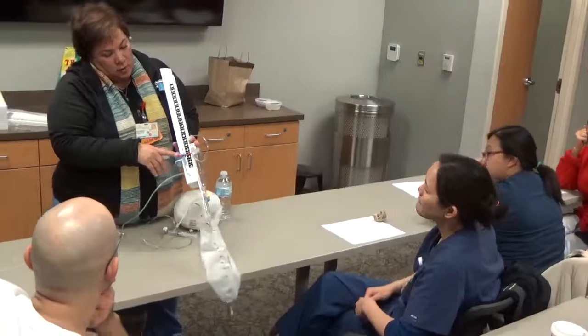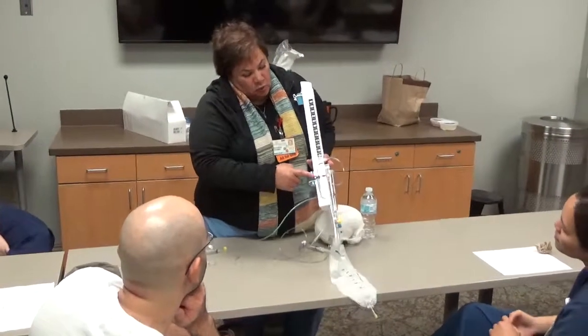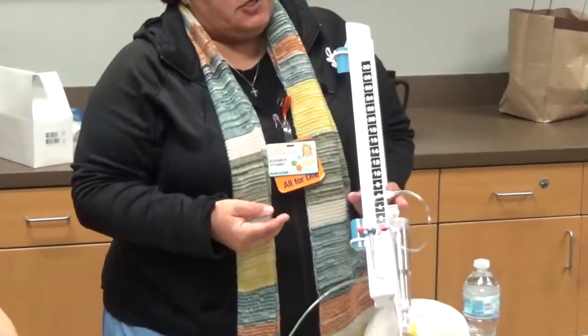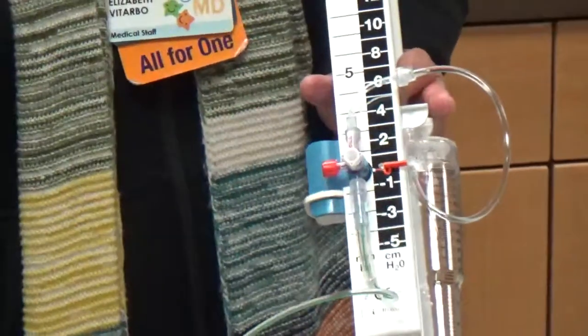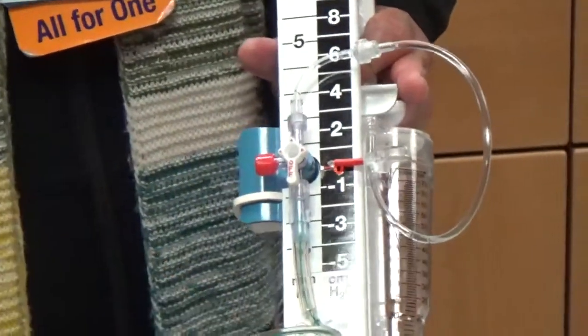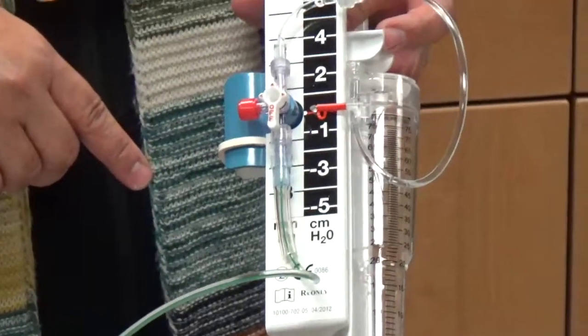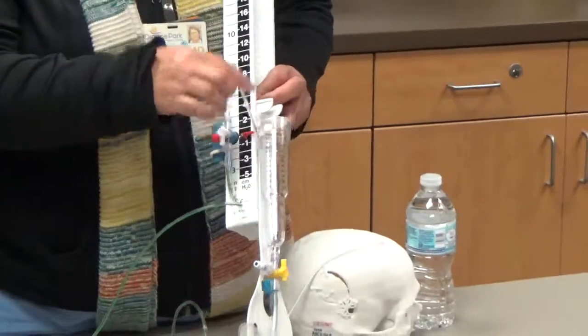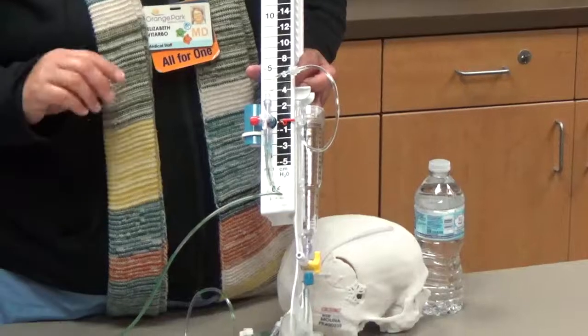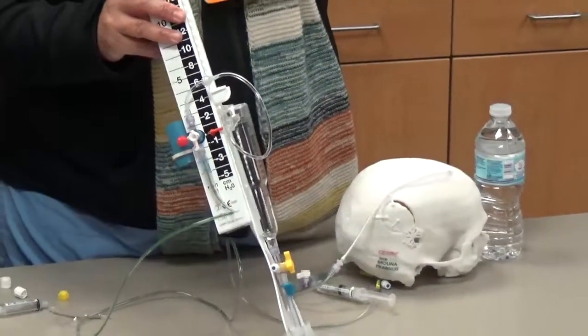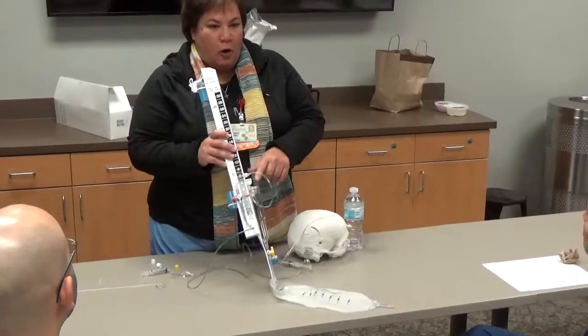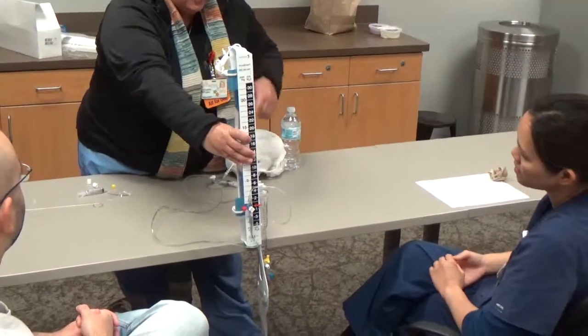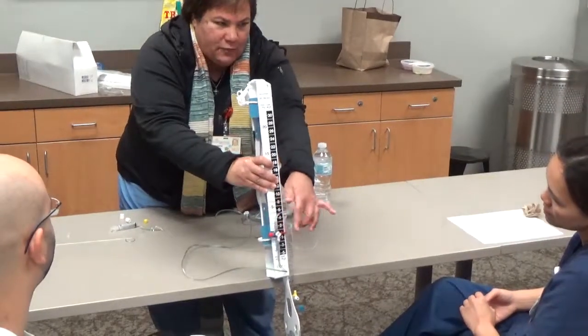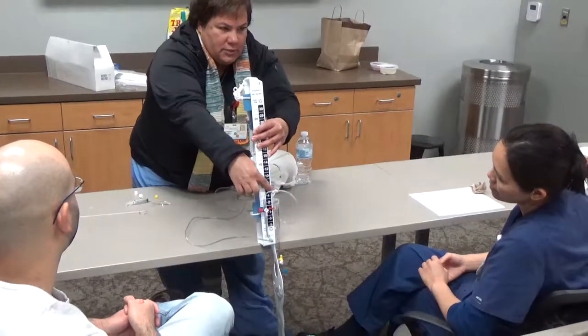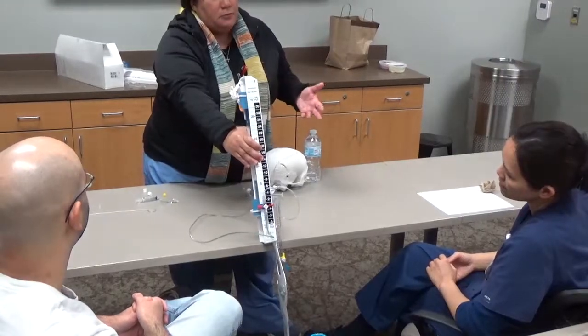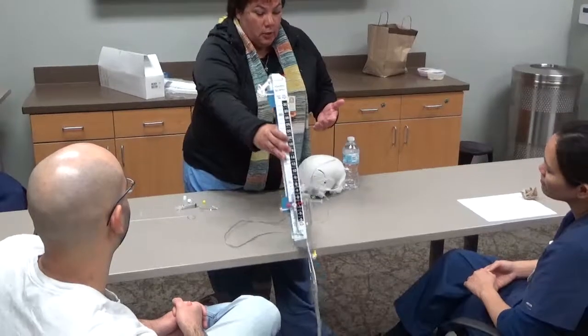So now, here's where the transducer is going to be connected, right? If you connect your transducer here, you flush it, right? No more pressure bags, you just flush your transducer. You connect it here. If you turn off to the patient drainage, where is that fluid column now connecting? It's now connecting to your chamber, right? Via this air filter, so long as it's intact and it's not wet, that air filter is open to the atmosphere, right? That's what zeroing means. So you are now open to atmospheric pressure. So if I have this at 0, and have that off to the patient, my fluid column is now straight to air, okay? So you don't need to remove any caps, that is your 0, okay?